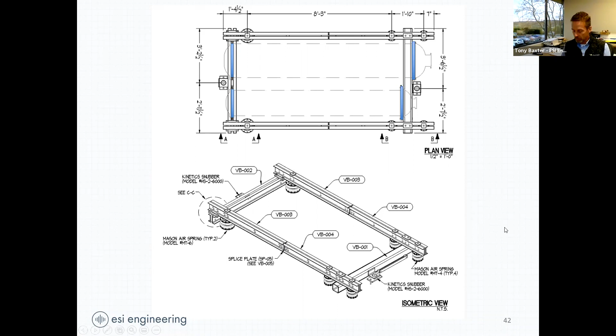The piping had some flex in it already, and there were spring hangers up above, so the piping could float a little bit. We didn't need to lift it very far, just far enough to get the load off the rubber and create an air gap down there.